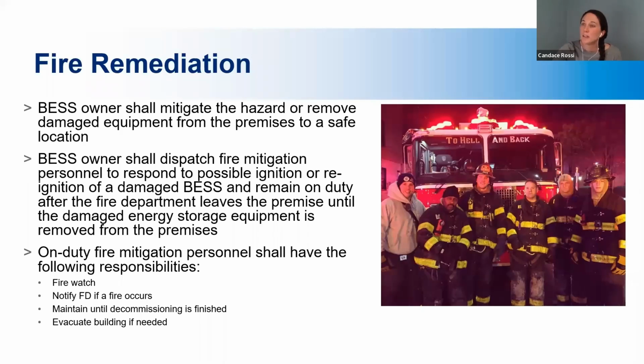This is also within the code, the fire remediation. The energy storage owner shall mitigate the hazard or remove damaged equipment from the premises to a safe location. The owner shall dispatch fire mitigation personnel to respond to a possible ignition or reignition of a damaged storage system and remain on duty after the fire department leaves the premises and until the damaged storage equipment is removed from the premises. So they have to provide these on-duty mitigation personnel, who shall have the following responsibilities: fire watch, notify the fire department if fire occurs, maintain until decommissioning is finished, and evacuate the building if needed.